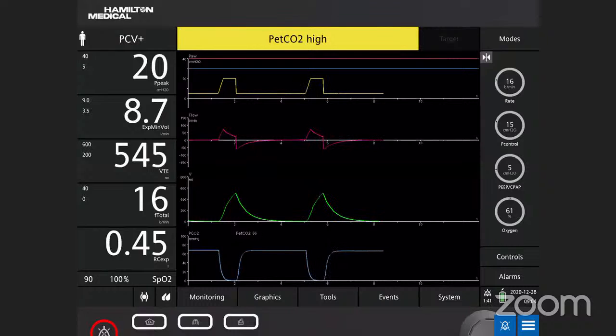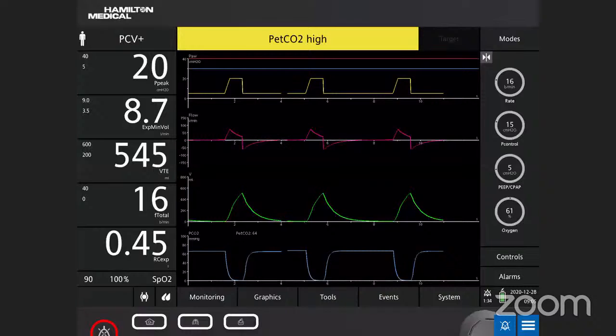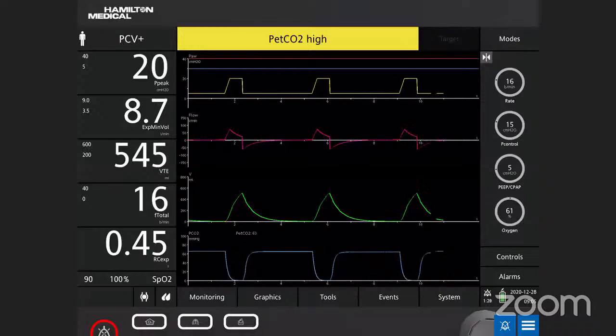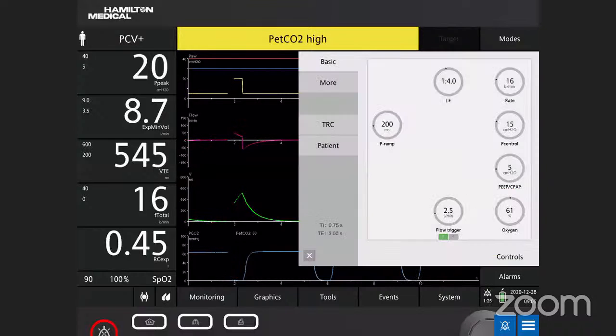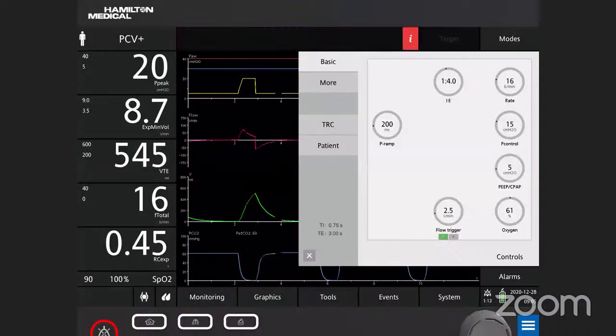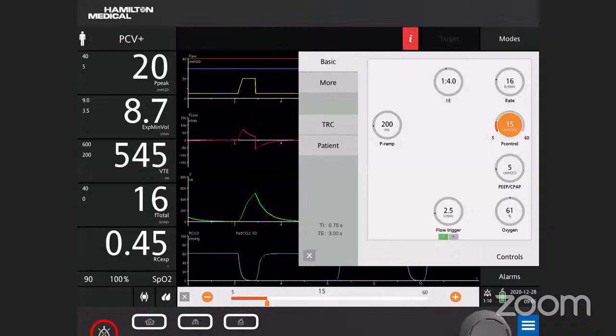However, the main two graphics that we always look at are the flow scalar and the pressure scalar. Volume scalar doesn't give much information. So this is your pressure control ventilation. The controls that you will keep in pressure control is the level of pressure control. Now this patient is only 50 kilos, right? You can see with 15 centimeters of water, the tidal volume generated is 545. That is too much.